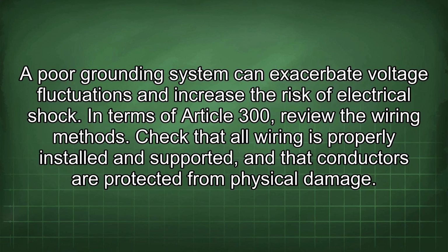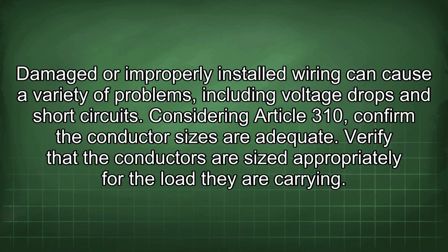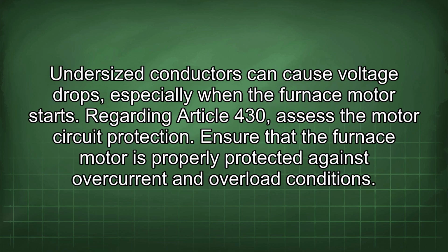In terms of Article 300, review the wiring methods. Check that all wiring is properly installed and supported, and that conductors are protected from physical damage. Damaged or improperly installed wiring can cause a variety of problems, including voltage drops and short circuits. Considering Article 310, confirm the conductor sizes are adequate. Verify that the conductors are sized appropriately for the load they are carrying. Undersized conductors can cause voltage drops, especially when the furnace motor starts.